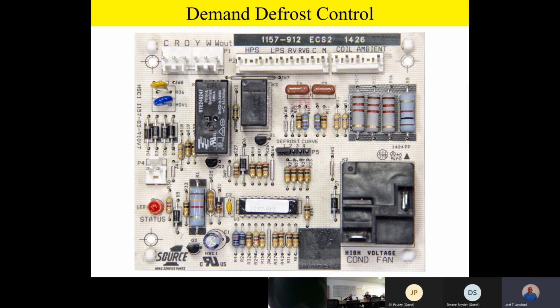Okay, good. All right, so as we take a look at the demand defrost control, I'm going to keep the picture up here a little bit as we talk about some of the differences between a demand defrost control and a time temperature control. The big difference, you'll notice in the upper right-hand corner of the picture, is that there are two sensors.